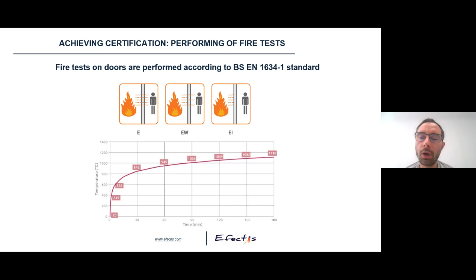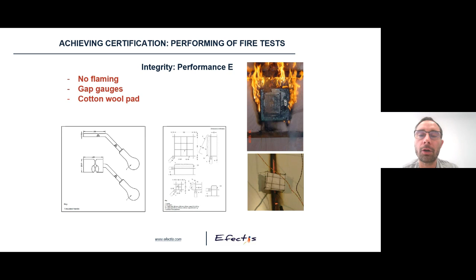For this performing of fire test and regarding the performances, E performance is linked to the fire integrity. It means that we have no flaming on the unexposed side. We have no gap gauges, no aperture, and we have no flaming of a cotton wool pad that we can apply on the unexposed side. For the higher performance, which is thermal insulation, it's not really used in the UK. It's mainly for European application, but in the UK, the most part of the doors are only E, but we'll talk about it anyway.